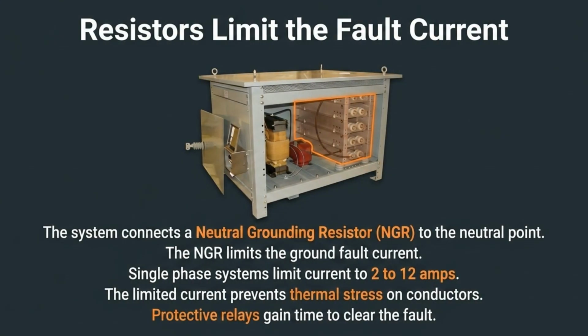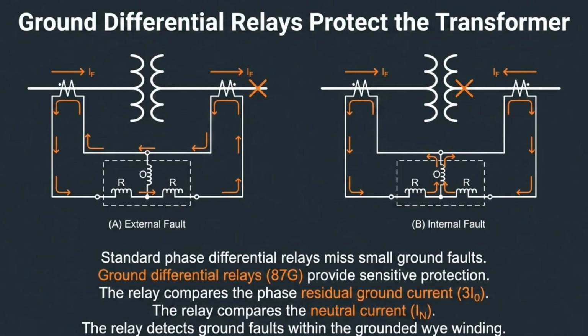To further enhance safety, a neutral grounding resistor is connected to the neutral point. This limits ground fault current, typically to between 2 and 12 amps, preventing thermal stress and giving relays time to clear the fault. Standard relays may miss small ground faults, so engineers use ground differential relays, or 87G. These relays provide sensitive protection by comparing the residual ground current to the neutral current.